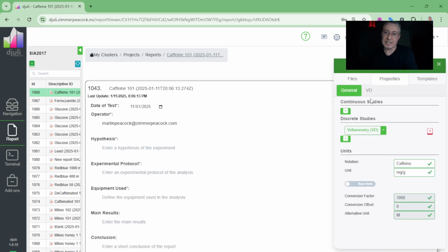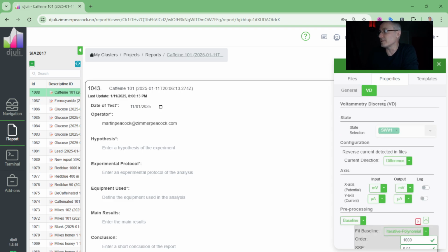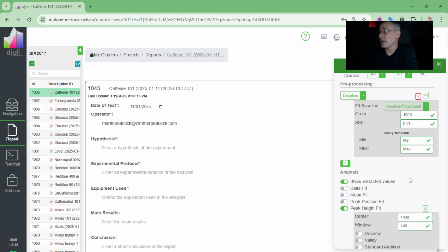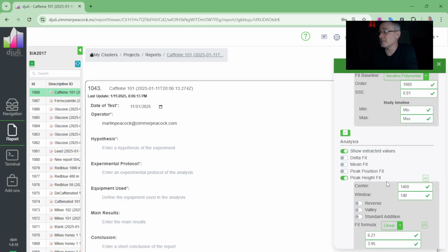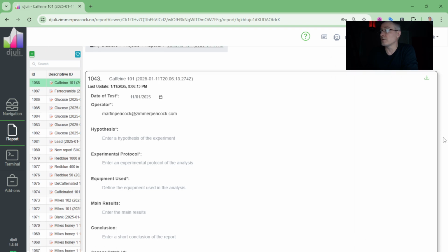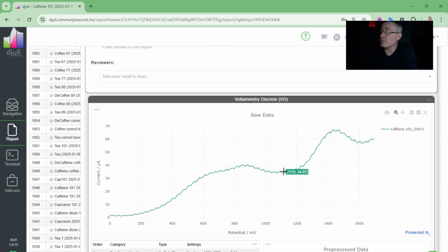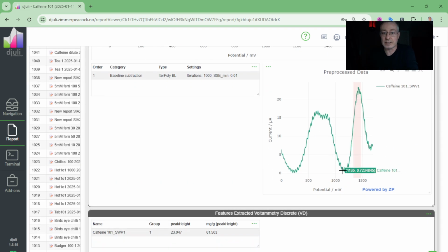It's got a sort of data pipe built into it, where we fitted a baseline, and then we've told it to do peak height versus that baseline. When I look here, you can see it's done a few things. It's forced the baseline to be here, rather than the baseline being up here and then trying to measure that height. I know you could do this manually, but in software, without any interference from me, it has forced the baseline down into here.